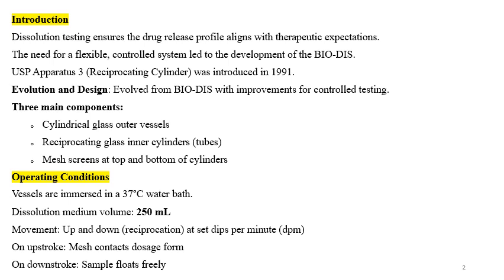Operating conditions for USP3 apparatus: vessels are immersed in a water bath at 37°C, and the dissolution medium volume is 250 ml. Movement is up-down at a set dips per minute — this up-down movement is reciprocation, which is why it is called the reciprocating cylinder. On the up-stroke, the mesh contacts the dosage form; on the down-stroke, the sample floats freely.